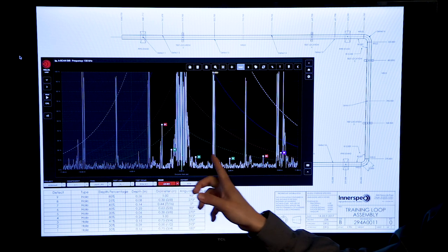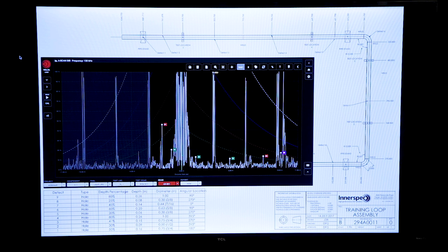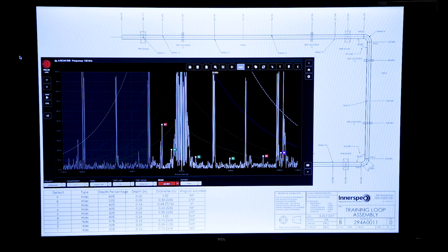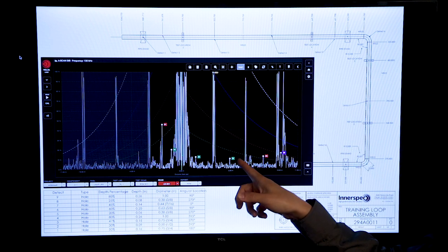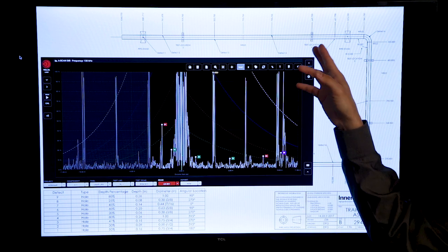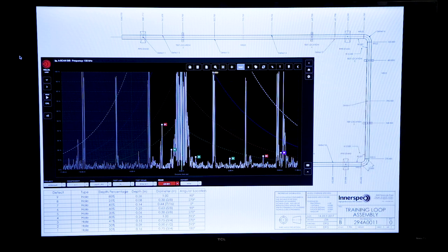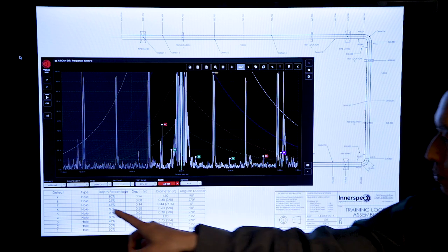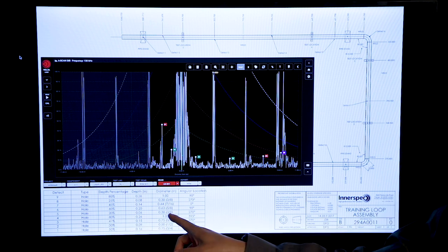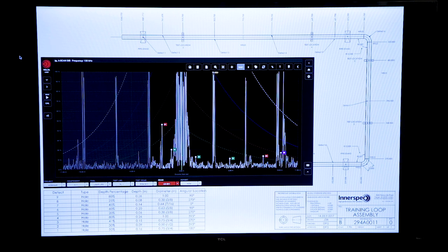Defect 4 is located 15 feet 11 inches away from the test location, and it is 80% depth and 1 inch in diameter. If you remember, we have 3 magnetostrictive strips located at test location 5, and they are all approximately 23 feet away from the test location. Defect 5 is located 27 feet away from the test location, and has a depth percentage of 20% and a diameter of 3/8 inch.